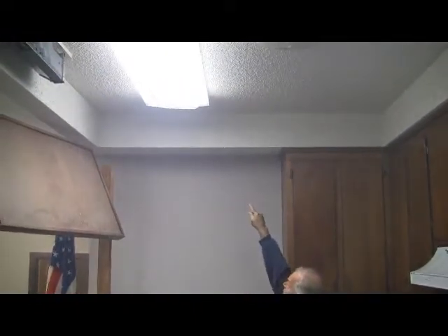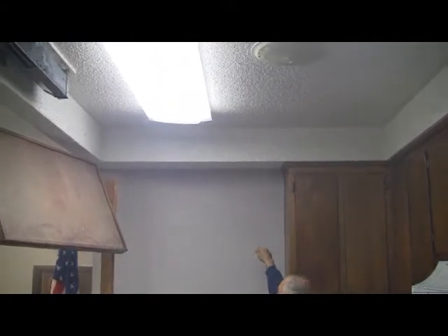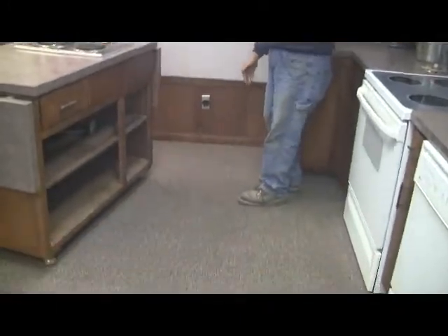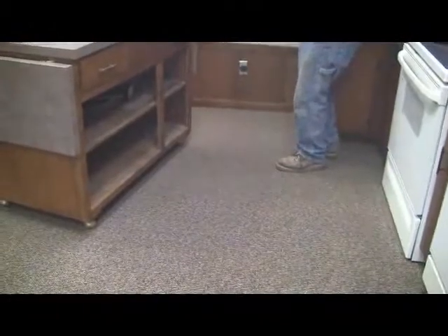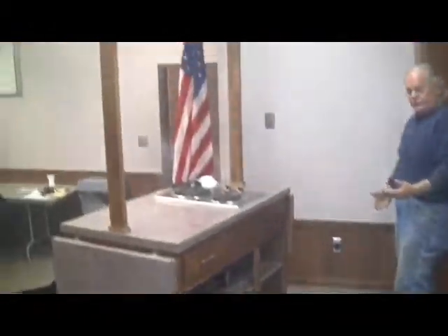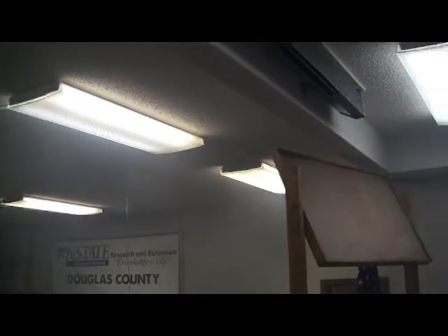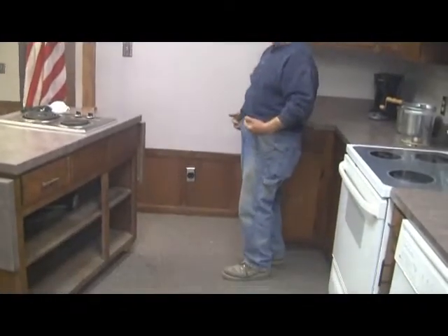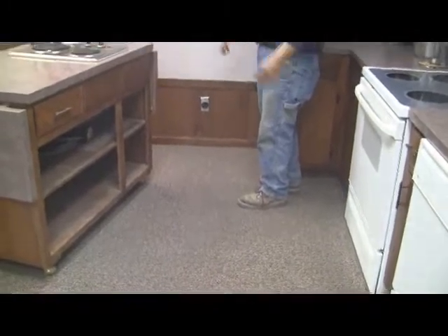We were sitting in the attic looking down inside of this little cavity and down the wall behind it. The open cavity of the stud framing behind this goes all the way down to the bottom of the floor underneath this stage that we're standing on, which is being used as the plenum for the furnace return system. So when this system is actually sucking air back to the furnace to recondition and send out through the supplies, it's drawing whatever the air is in the attic into the system through this wall cavity back to the furnace to recondition. Air conditioning, hot air.